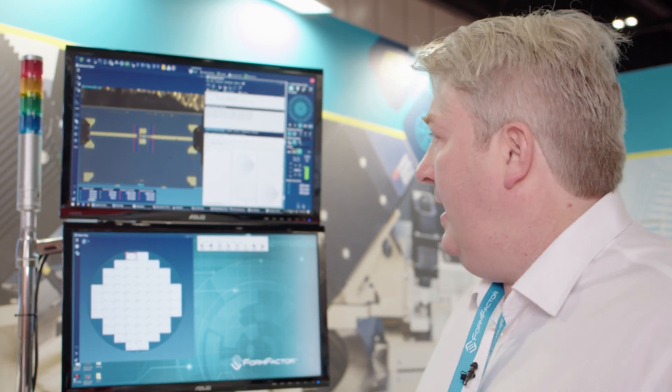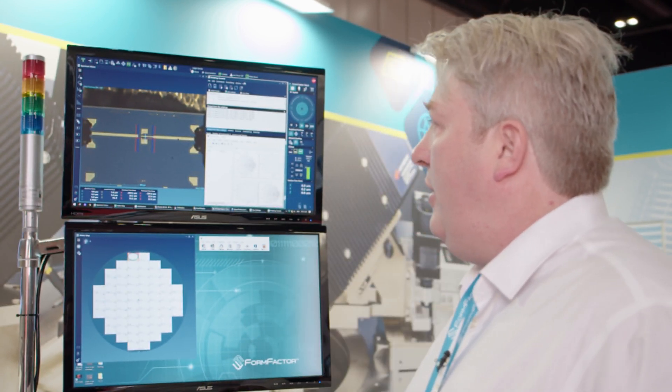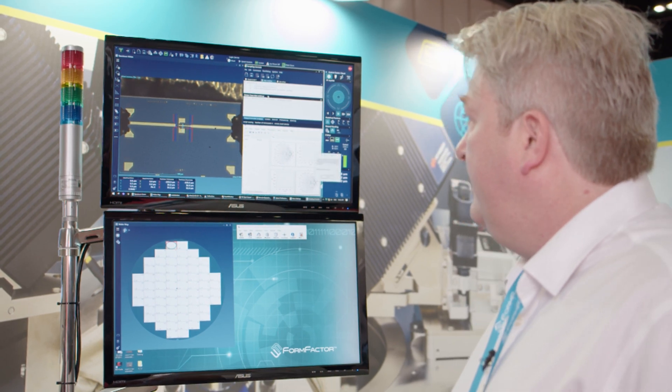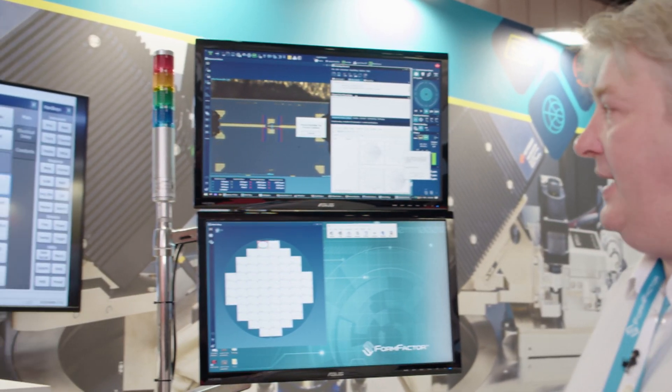Now that we've got a calibrated vector network analyzer, we're going to take real-life measurements of an active device using Python. You can see we have the scripting console native to Velox, our probe control software, by which we can run Python scripts. Using Python we can do some powerful things — one of those is connecting to WinCal using WinCal Remoting, which has a big library of functions. We're going to apply a bias using a GPIB-controlled power supply and simultaneously take those active measurements. Our probes are already in place on the device under test — it will provide a series of biased measurements.